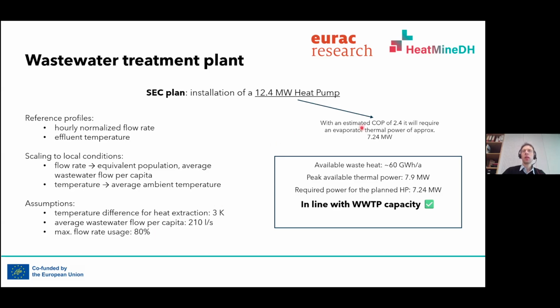In terms of COP, we did a first conservative analysis, calculating the average COP by combining the temperature of the source in the curve shown before and reaching the supply temperature of the district heating system, so even slightly more than 100 degrees in certain seasons. This is a conservative assumption, because proper operation of the heat pump could be limited in some periods, or coupled with other sources to limit the temperature output of the system.